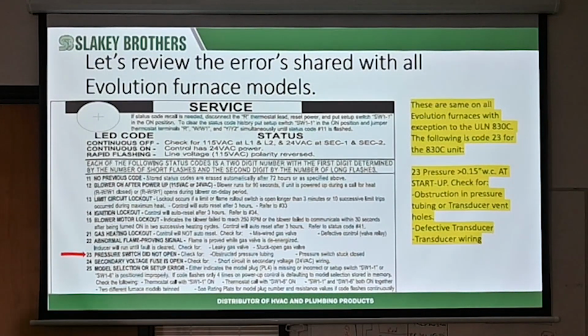Yeah, I had this just 3 days ago. And I found that I need to take the chip from the old board. Sometimes I didn't know about it. It fits on there well, but there's been one or two weird ones where it fell off and it's sitting on the bottom of the furnace. On a brand new unit, they get a code 25 and that little chip is missing. So that little chip's got to be in there. If you replace one board, make sure you swap that chip.